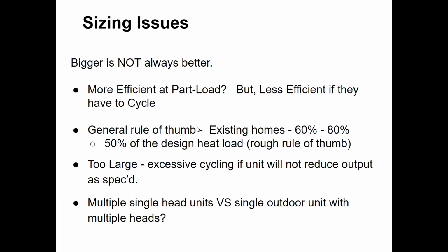Just a comment about sizing, because this is something that drives many of us crazy who specialize in HVAC. Bigger is not always better. Even your HVAC guy might tell you bigger is better. Your HVAC person might come and say, 'Rule of thumb, I think you're going to need 60,000 BTUs for your home because that's what your current gas furnace delivers.' Invariably across the board, you do not need that much capacity. You probably need half of that for 99% of the year, in 99% of the years. I know you don't believe me because you live in Fairbanks, but this has been proven over and over again. The amount of capacity you need for a home with a well-running heating system is not nearly the amount that you think it is.